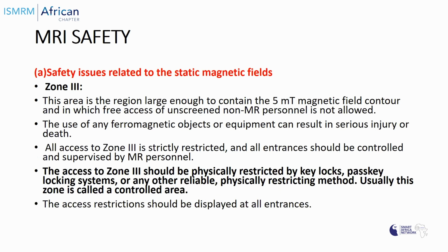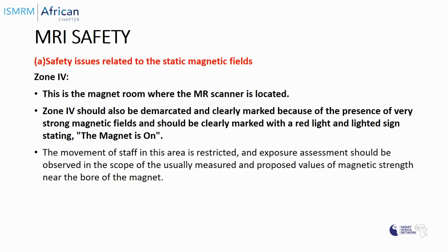Then we have Zone 3. Access to Zone 3 should be physically restricted by locks, passkey, locking systems, or any other reliable physically restricting method. Usually this zone is called the controlled area. Then Zone 4. This is the magnet room where the MR scanner is located. Zone 4 should also be demarcated and clearly marked because of the presence of very strong magnetic fields. And this should be clearly marked with a red light and lighted sign stating the magnet is on.